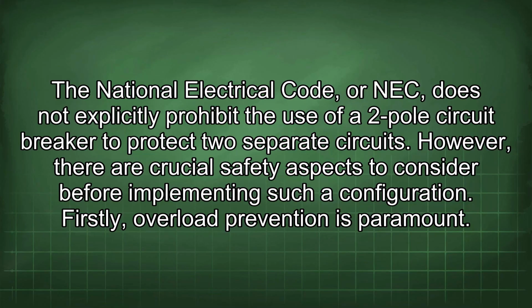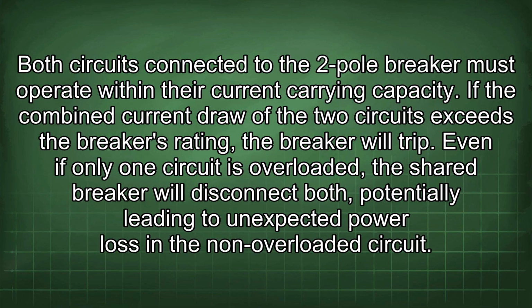The National Electrical Code, or NEC, does not explicitly prohibit the use of a two-pole circuit breaker to protect two separate circuits. However, there are crucial safety aspects to consider before implementing such a configuration. Firstly, overload prevention is paramount. Both circuits connected to the two-pole breaker must operate within their current carrying capacity. If the combined current draw of the two circuits exceeds the breaker's rating, the breaker will trip.